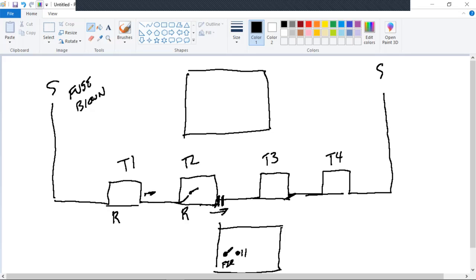Guys, remember what the fault indicator is looking at. A, all right, B is here. It's reading T2 transformer as well. There you go. The fault occurred in the transformer. Remember, it's watching the transformer itself too. It's on the transformer. So if you're showing red, the transformer itself is bad.